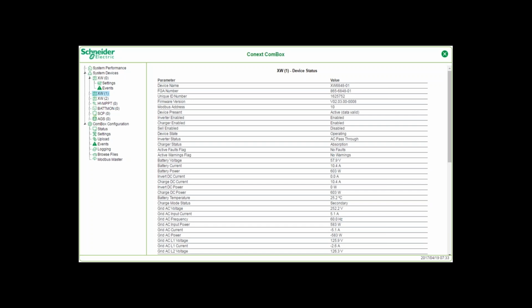Here we see the device status screen for the XW Plus, which provides a wealth of real-time information about the state of the unit. AC and DC voltages, currents and power, fault status, firmware, Modbus address, etc. So say a customer called in and said, hey, my system isn't selling, it would be very quick and easy just to access this device status page and go down to see if sell is enabled. And if it's disabled, it's just a matter of enabling sell mode and he's back in business.